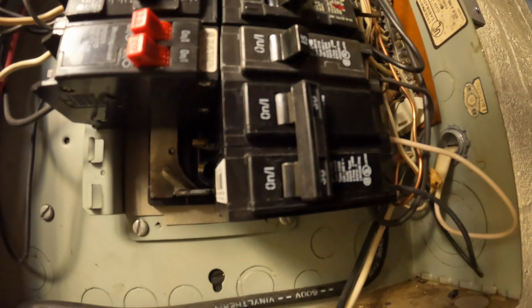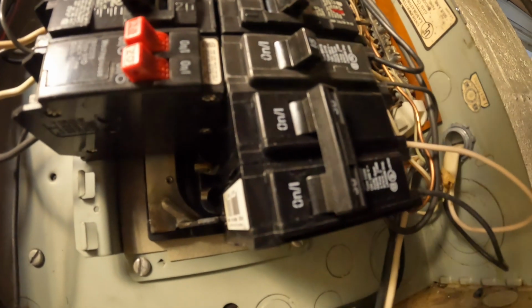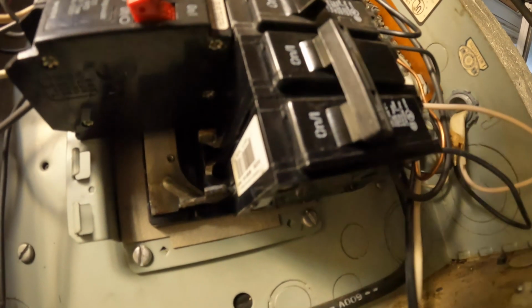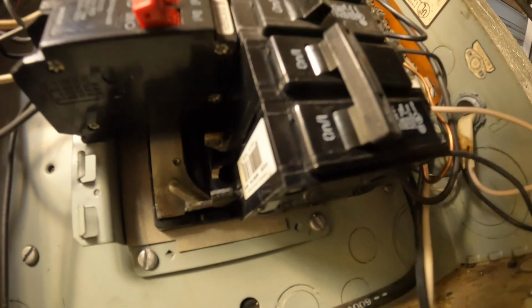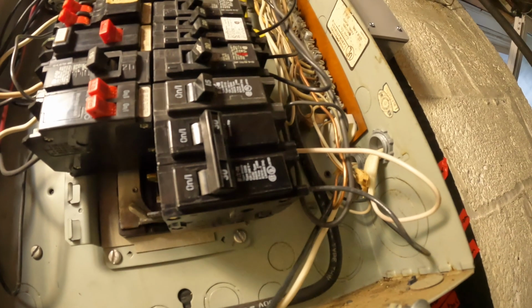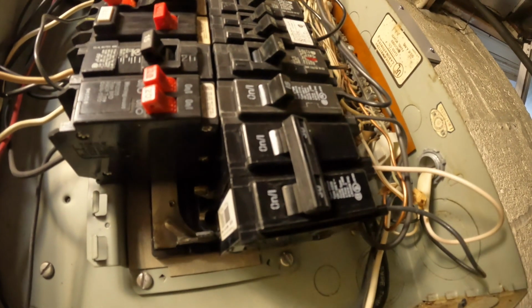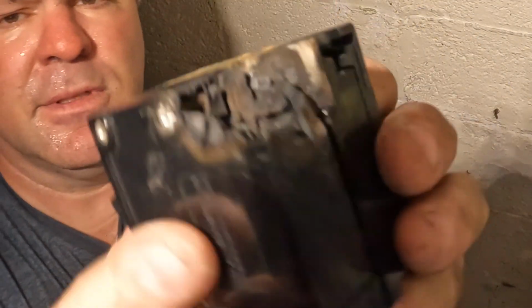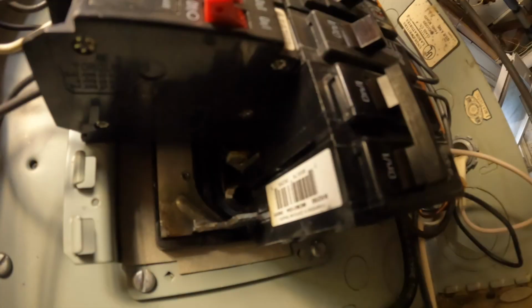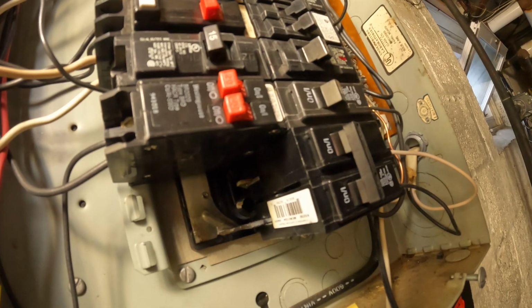This customer is a longtime subscriber to my channel. His name is Tyler. Hello, Tyler. So Tyler called me because the air conditioning condensing unit circuit breaker was buzzing, and when he had an HVAC company come out and take a look, he noticed that this circuit breaker was burned up onto the bus bar. So Tyler wanted me to change this panel and upgrade to a 100 amp 30/60 circuit space panel.